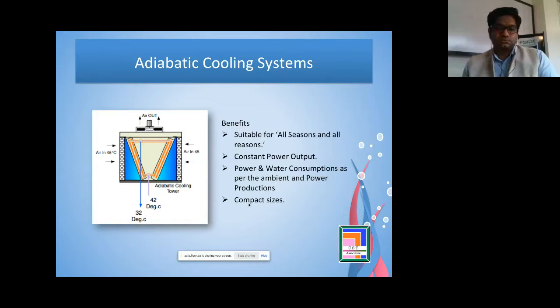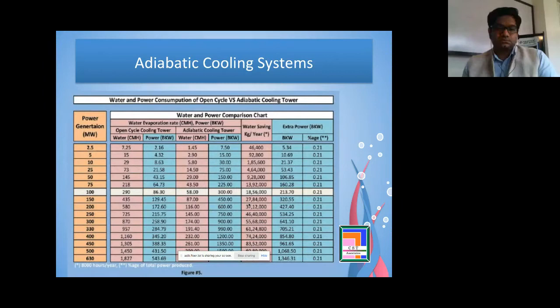1575 fans. Whereas I have designed adiabatic cooling towers which will cater to 10 megawatt each using only one fan. So 10 megawatt means if we have a 630 megawatt power plant, only 63 fans will be there, as compared to the 1575 fans which the general industry is offering. And these are very big size coolers. When we go for a bigger diameter of fan, the efficiency of the fan increases. Once the efficiency of the fan increases, there is a reduction in the power consumption.